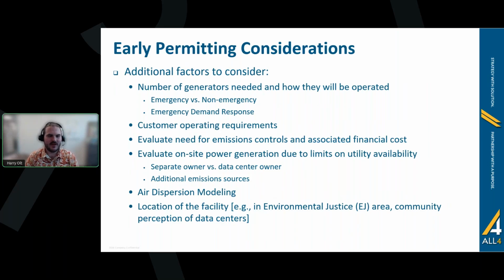An additional factor to consider early in the permitting process is the number of generators needed and the operating mode. As mentioned with the planned size of the data center, the number of generators and how they will be operated will be a key factor that affects air permitting. Will the generators only be used as emergency units, or will they be used for non-emergency purposes too? And if so, what type? That not only affects the permitting, but may also dictate what engines should be purchased.